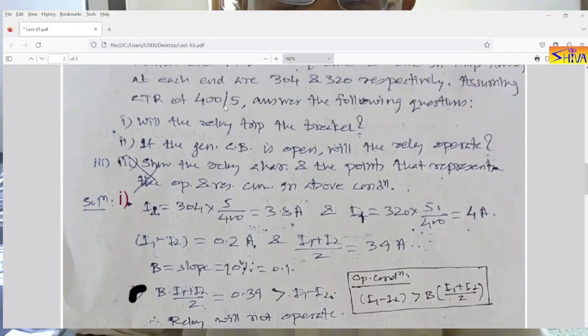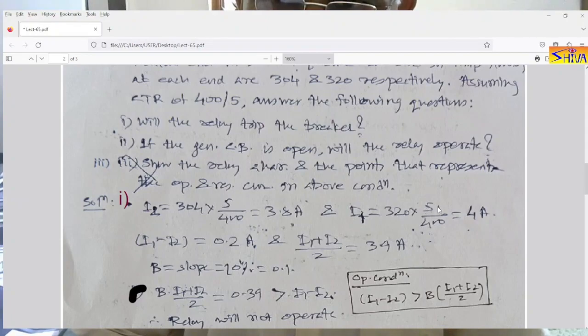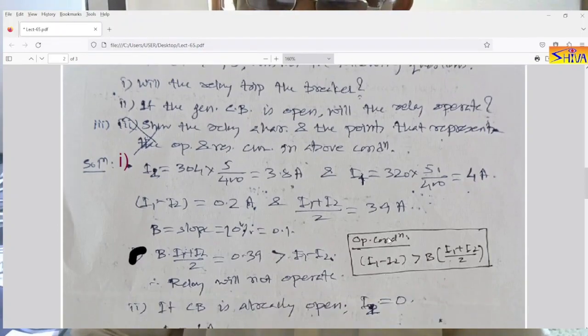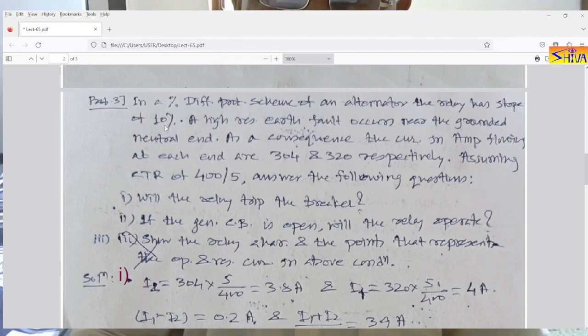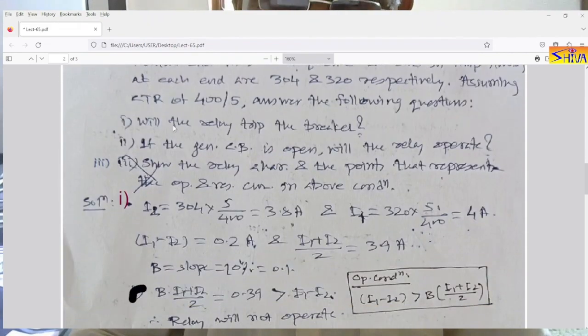The CT ratio is given as 400/5. Computing secondary-side currents: I2 = 304 / 80 = 3.8 amperes; I1 = 320 / 80 = 4 amperes. For the percentage differential relay, the operating condition is: I1 − I2 > B × (I1 + I2) / 2, where B is the bias (slope of the characteristic). The bias is given as 10%, that is 0.1.